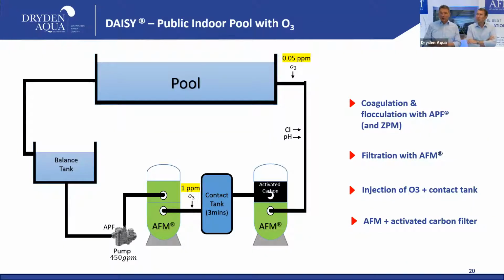Okay, that's perfect. That helps. But then you have to go for low dose ozonization. Yes, like 0.1, maximum 0.2 grams per water that you treat. And this is a completely different story on the cost side.